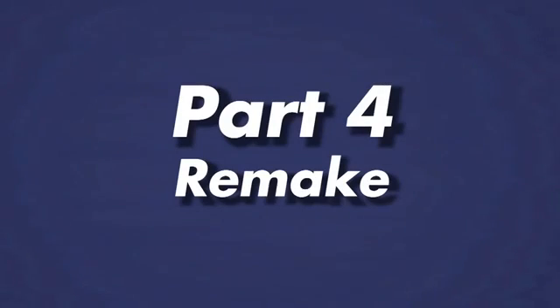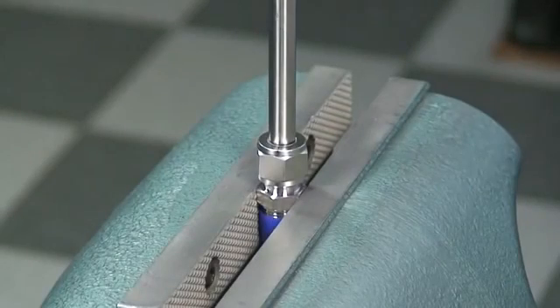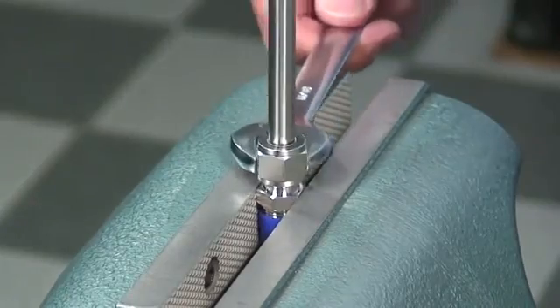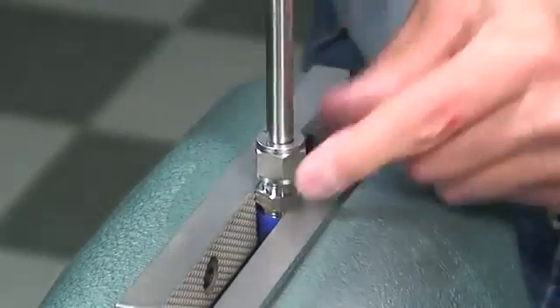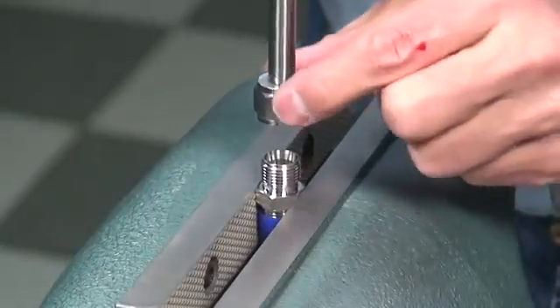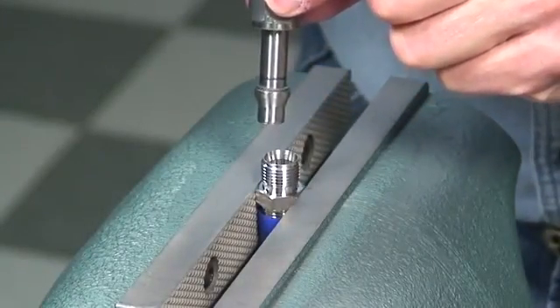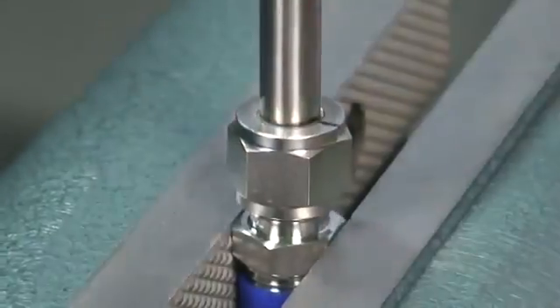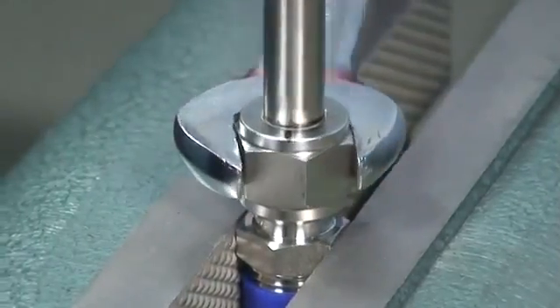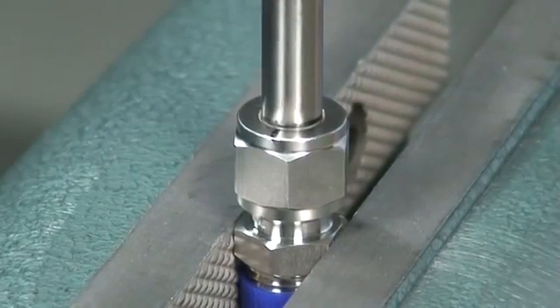One benefit of the unique Gyrolok design is that it can be remade many times, saving you valuable time and expense. The controlled ferrule drive and the sizing angle avoid the risk of over-tightening, which allows for multiple remakes. Tubing-ended valves can be easily reused and need not be thrown away. To remake a fitting, loosen the nut and pull the tubing and ferrule assembly from the body. Then reinsert the end component into the fitting body and tighten the nut until finger-tight. While supporting the fitting body, use a wrench to tighten the nut until a sharp rise in torque is felt, then snug it tight. Typical reassembly requires approximately ¼ turn from the finger-tight position.